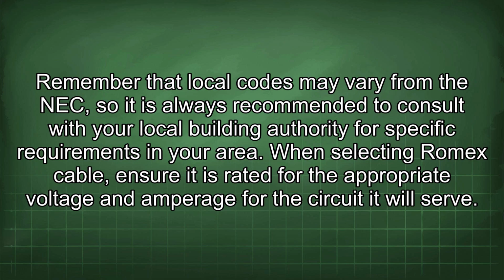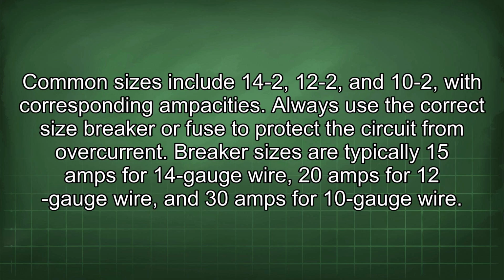When selecting Romex cable, ensure it is rated for the appropriate voltage and amperage for the circuit it will serve. Common sizes include 14-2, 12-2, and 10-2, with corresponding ampacities. Always use the correct size breaker or fuse to protect the circuit from overcurrent. Breaker sizes are typically 15 amps for 14-gauge wire, 20 amps for 12-gauge wire, and 30 amps for 10-gauge wire.